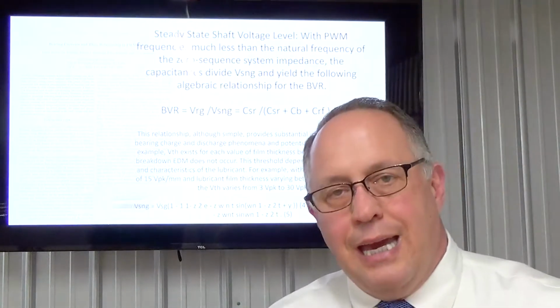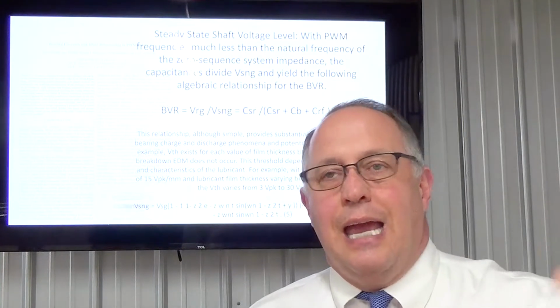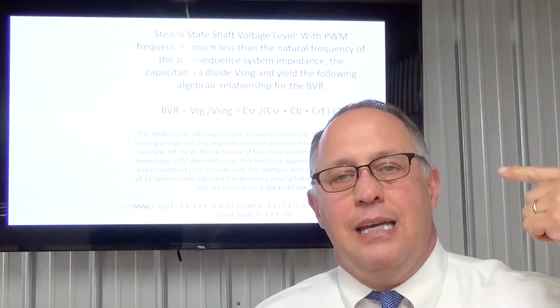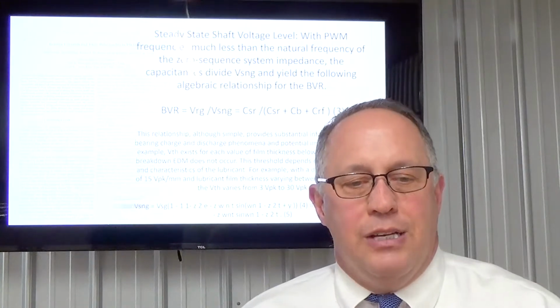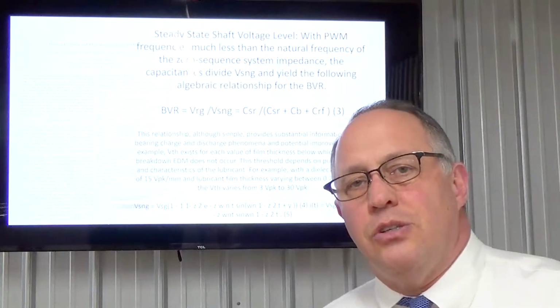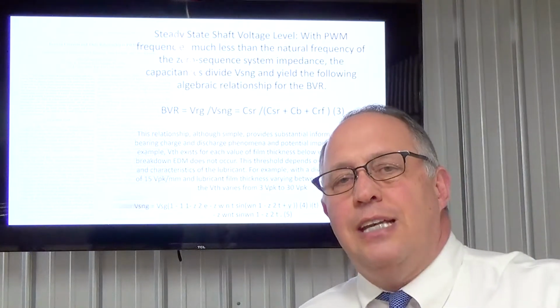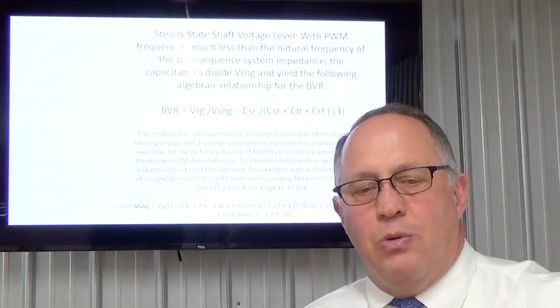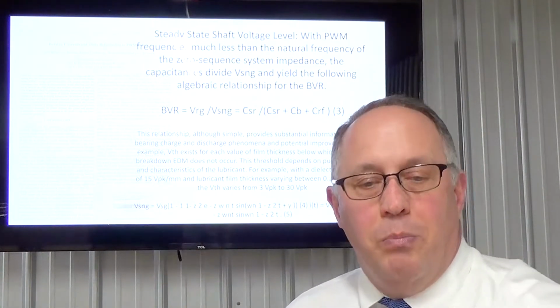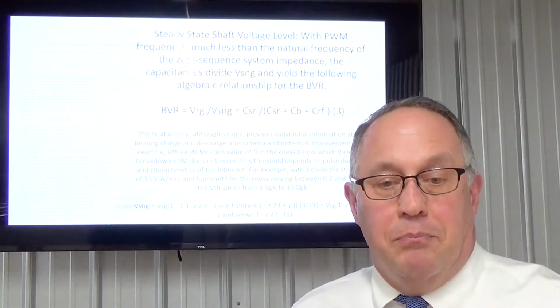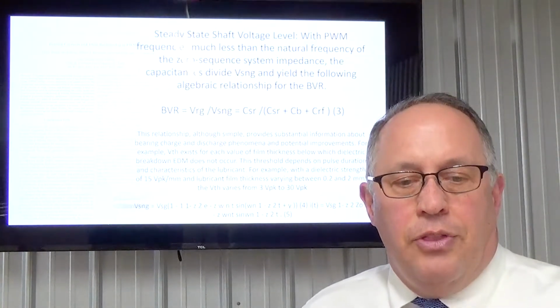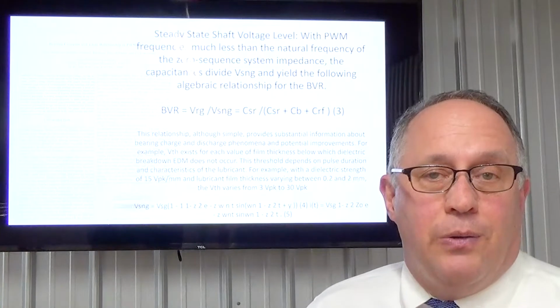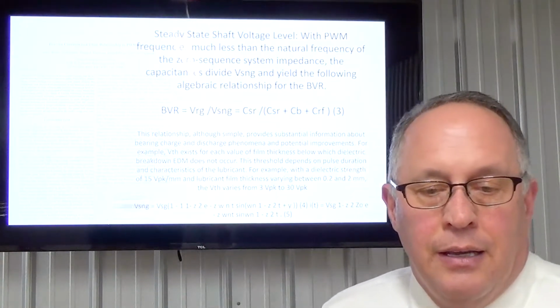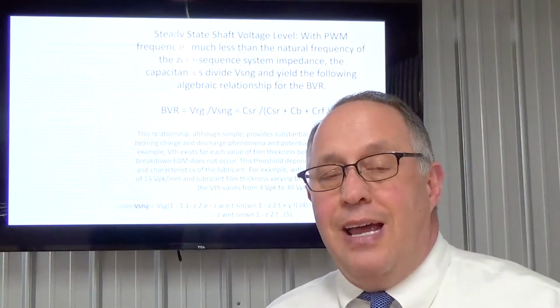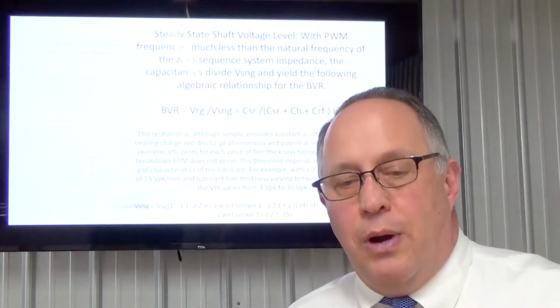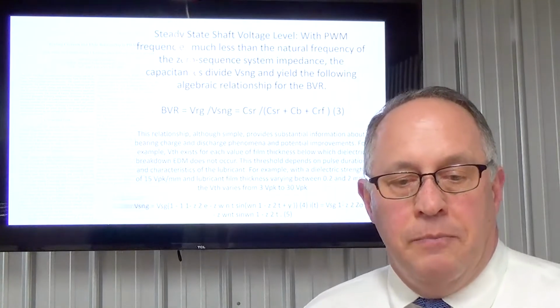A lot of time we don't care necessarily what causes it. Can we fix it? Leave the smart folks to doing the equations. But the following things can be reasons to cause that. Number one, the VFD location, the actual location of the drive in relationship to the motor being driven can cause additional effects. The carrier frequency at which the VFD is operated, the motor size, as we have found, larger motor size, the more prevalent it is to find this type of shaft voltage.